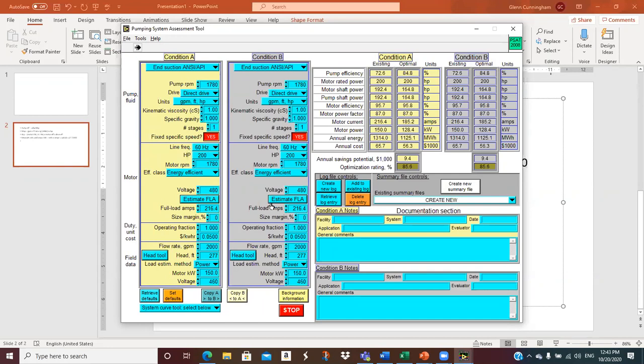And all of that's in this 277. Let's say that by opening the valve and trimming the impeller, I can drop that 277 feet to 200 feet, because I'm dropping 77 feet across the valve. So I can open the valve, trim the impeller, and reduce my head in the system by the 77 feet across the valve. So everything's the same, let me change this to 200. Now, if you look at A to B, existing A to existing B, well, now just a minute. I don't look so good. I'm using the same amount of energy.